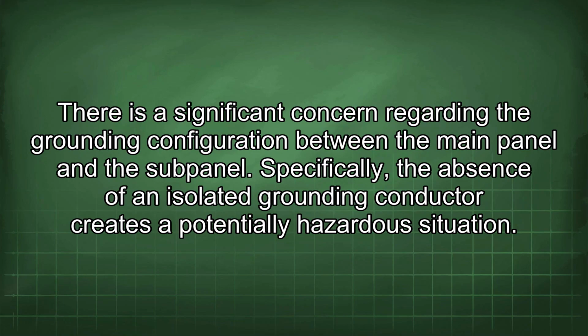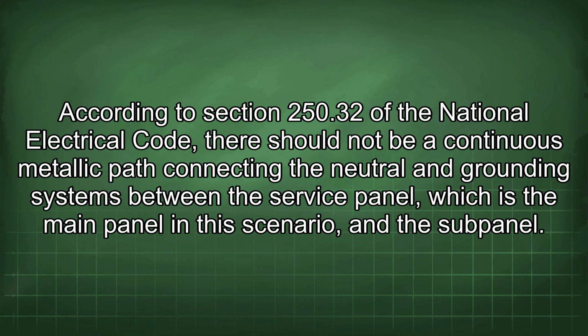There is a significant concern regarding the grounding configuration between the main panel and the subpanel. Specifically, the absence of an isolated grounding conductor creates a potentially hazardous situation. According to Section 250.32 of the National Electrical Code, there should not be a continuous metallic path connecting the neutral and grounding systems between the service panel, which is the main panel in this scenario, and the subpanel.